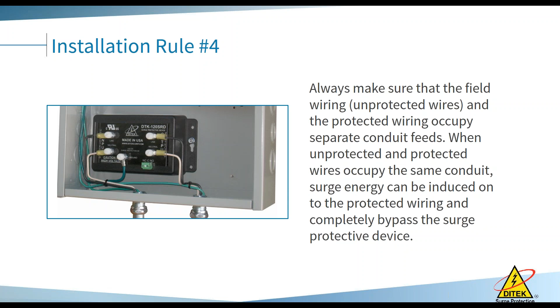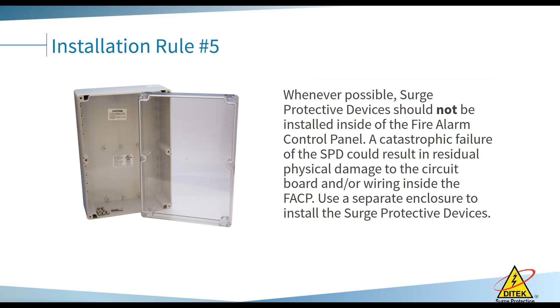Again, you want your protected and unprotected wires in separate conduits as well. We see a number of projects where they pipe it into a box and then out the box into the same conduit, and then they'll just couple over and bypass the surge like this. This is a much better install. Installation rule number 5, don't put them inside the fire alarm control panel, put them in their own box.